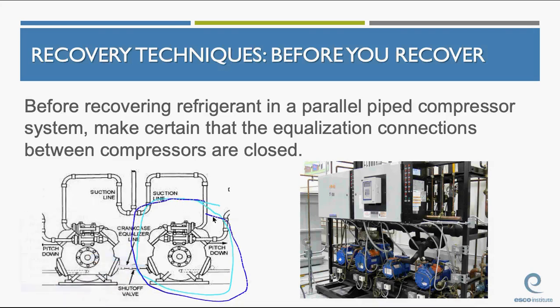Let me change my pen color. Okay, the compressor on the right is dead. You're having to change that compressor. So you actually have to close the shutoff valve that's on that equalizer line so that you can just recover refrigerant from this one compressor. Okay, because in a supermarket rack system like you have here, you don't shut down the entire thing to work on one compressor. You're only shutting down the compressor you're working on and you let the rest of the system handle the load. Okay, but you have to close the valve on that equalizer line because you can't recover refrigerant from a single compressor unless it's completely isolated. Does that make sense? Any questions on that?